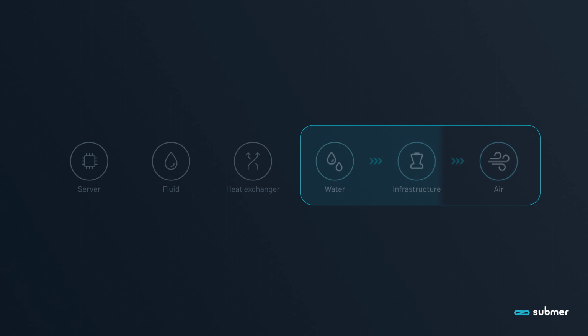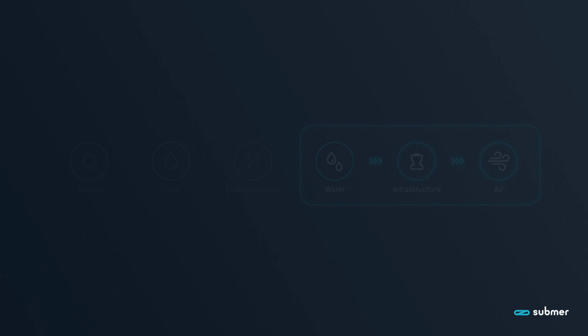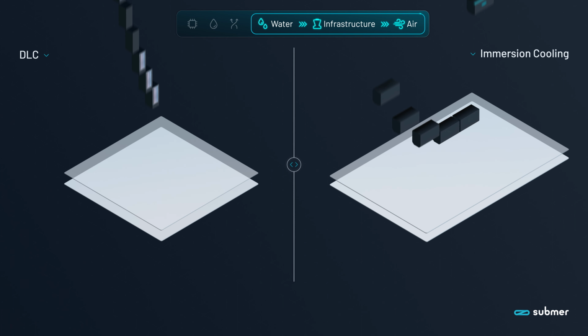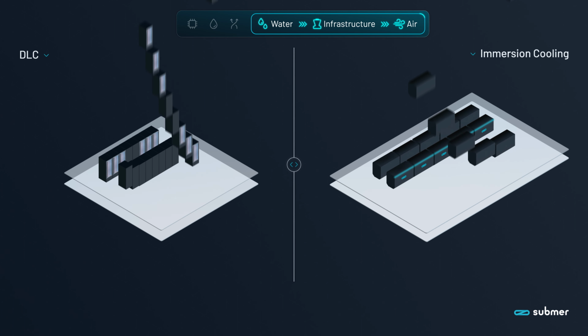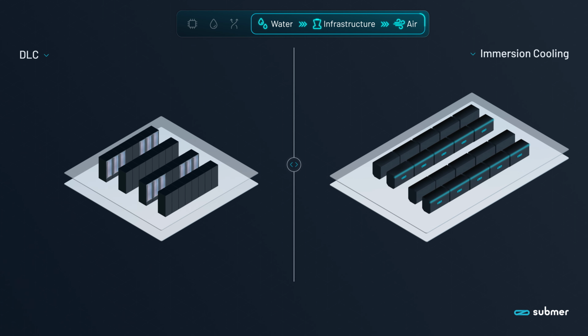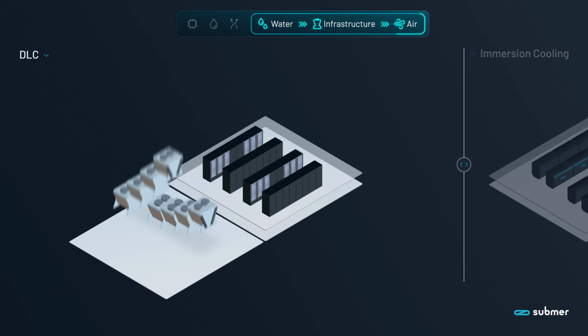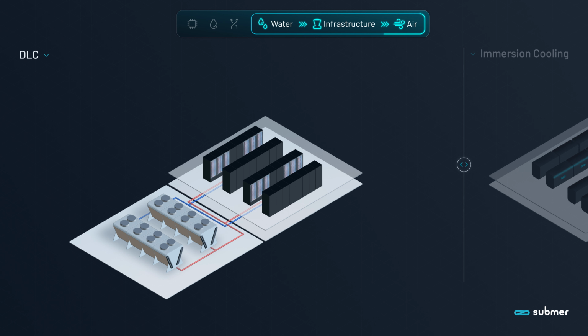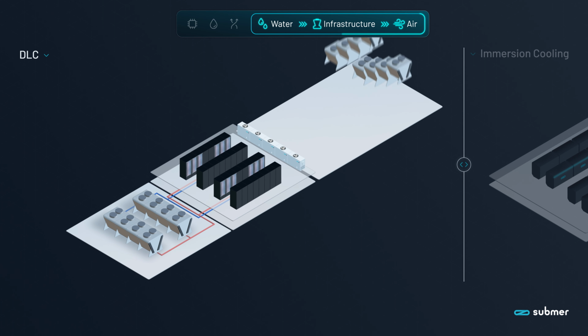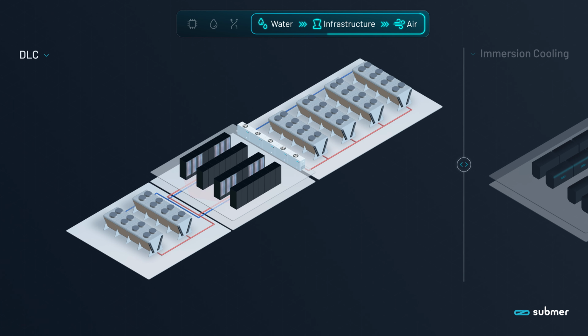In the final stage, the secondary fluid releases the accumulated energy via the heat rejection infrastructure. Usually, there are so many chips and servers needed that racks and pods are deployed by hundreds. Components like network switches may need air cooling, but are excluded here. With DLC, the portion of the heat handled by the secondary fluid requires a relatively small heat rejection system. In contrast, the portion handled by air cooling needs large air handlers and heat rejection systems due to the lower thermal performance of the air compared to a liquid.